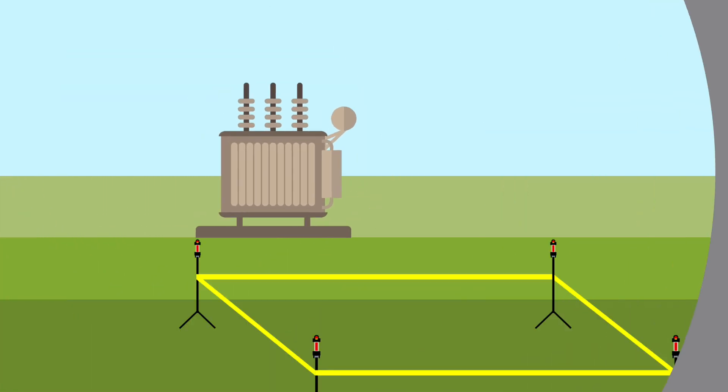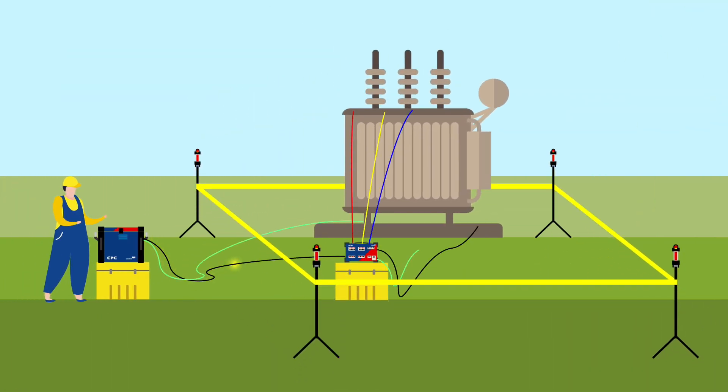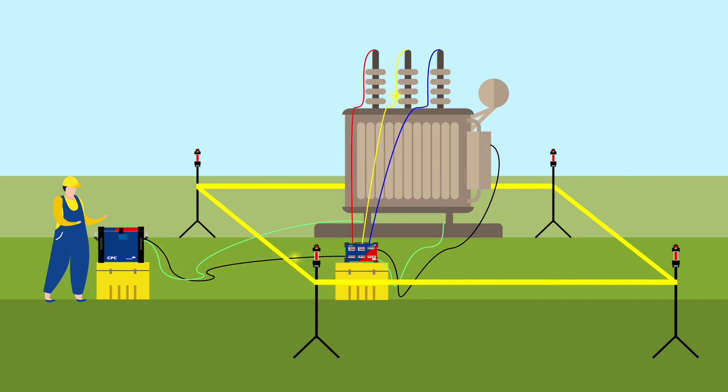By combining the CPC-100 with the CPSB1, you can test all three phases and the tap changer automatically. Thus, power transformer testing becomes faster and safer as the rewiring effort and the likelihood of measurement errors are minimized.